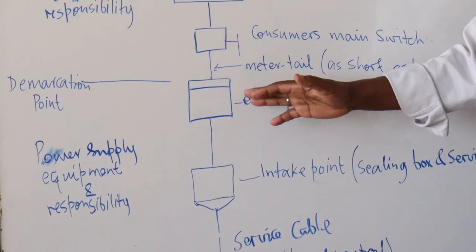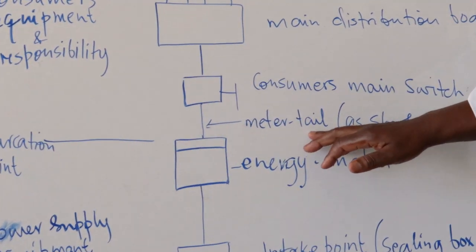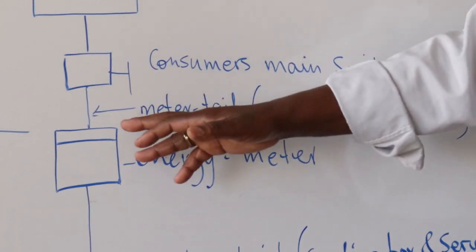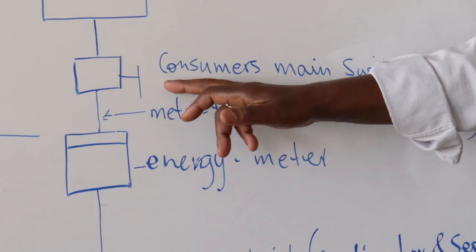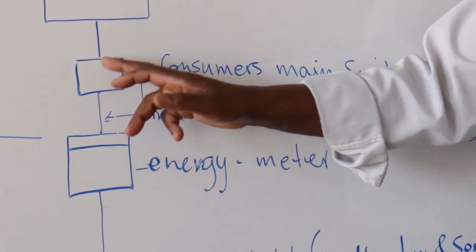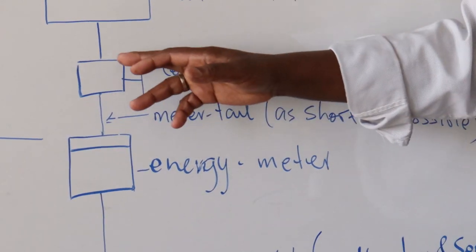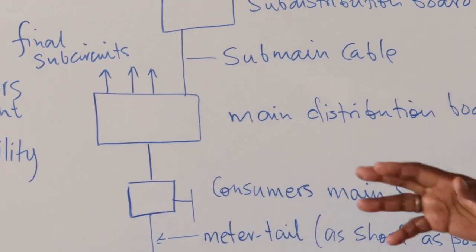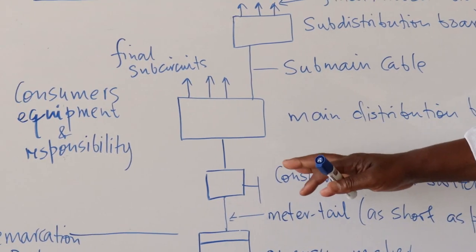From the energy meter there is what used to be referred to as the meter tail, which should be as short as possible so that nobody can interfere with it. This comes to the consumer's main switch, which is a double pole, before it goes to the main distribution board or consumer control unit.